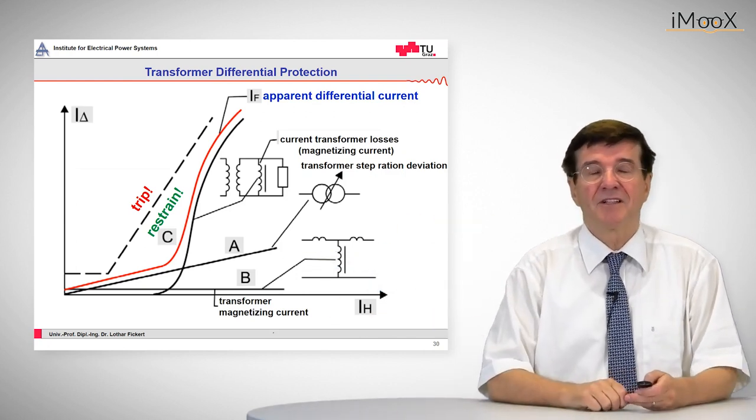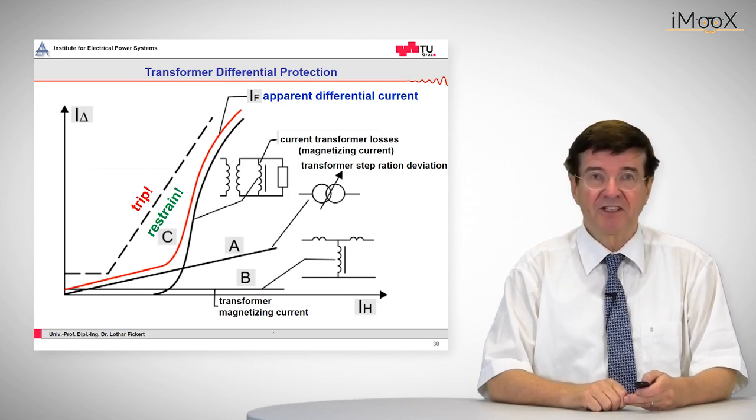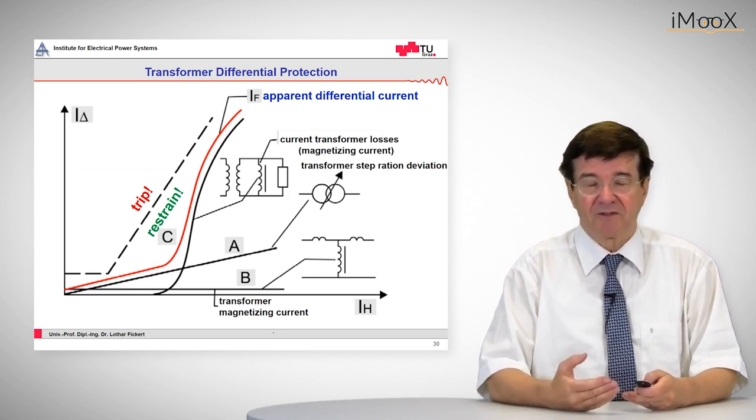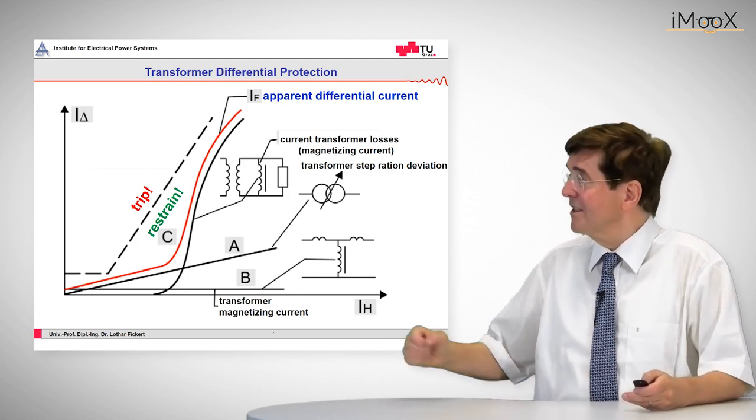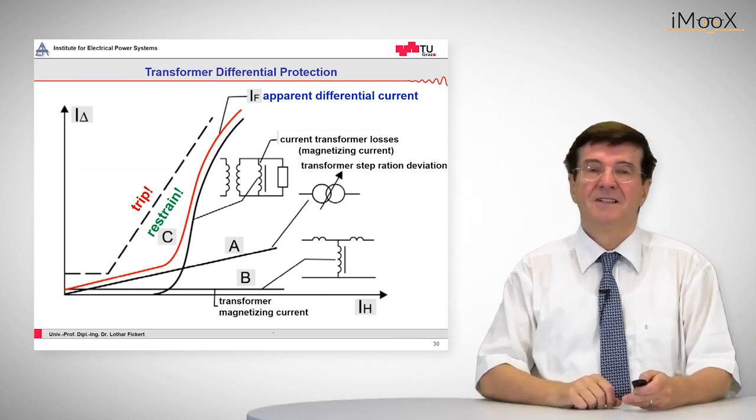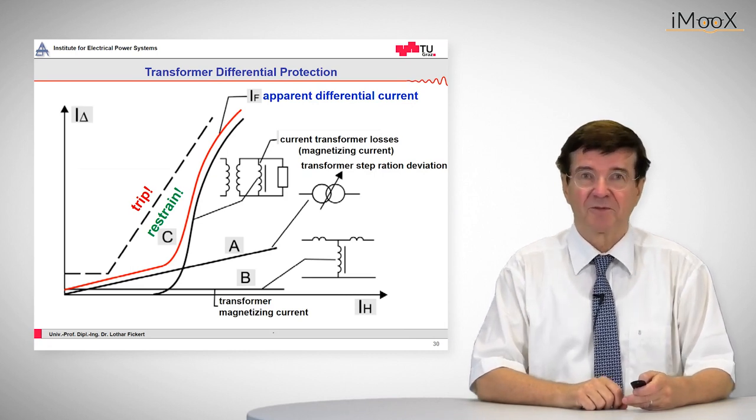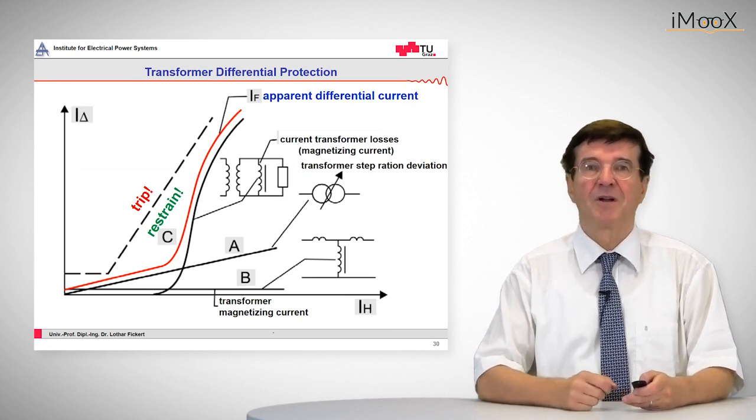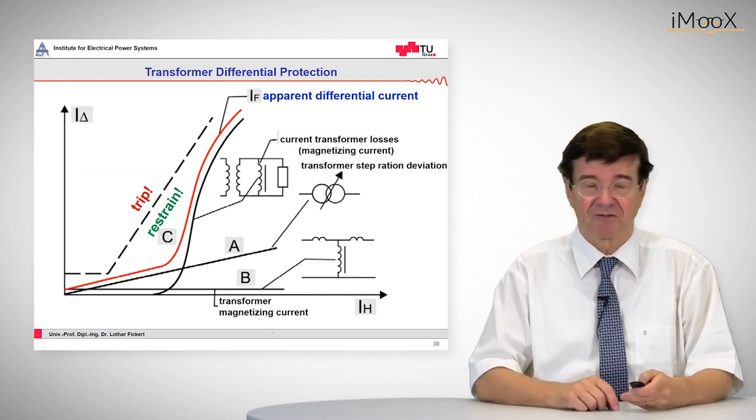Also we can have in a transformer, due to the effect of saturation, a saturation differential current that comes up in heavy through fault conditions. All these add up to this S-shaped accuracy curve, and the differential protection should not pick up if we are below this curve. If we are above, then we have a severe fault and the trip must occur.